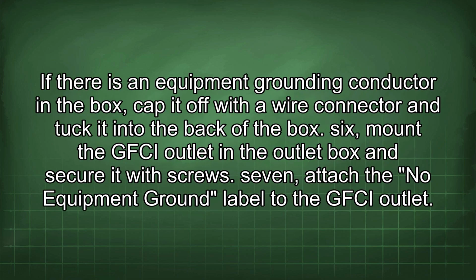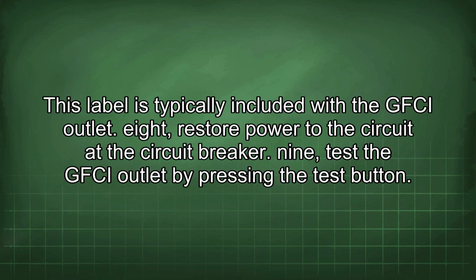If there is an equipment grounding conductor in the box, cap it off with a wire connector and tuck it into the back of the box. 6. Mount the GFCI outlet in the outlet box and secure it with screws. 7. Attach the "No Equipment Ground" label to the GFCI outlet. This label is typically included with the GFCI outlet.